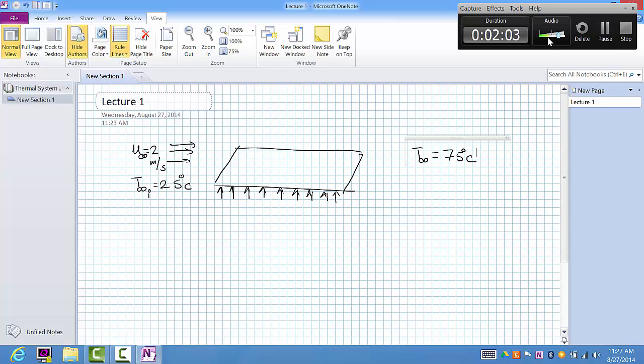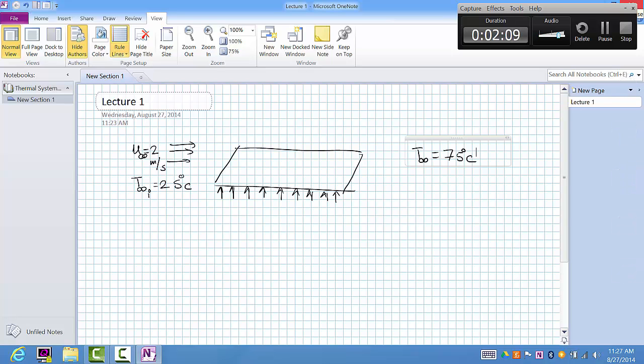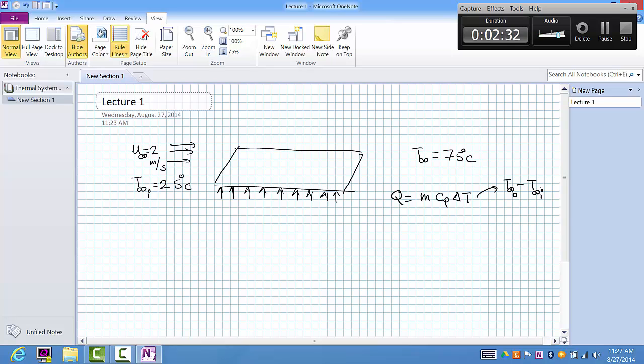You can draw on your thermodynamics knowledge and readily calculate the required heater capacity. The rate of heat required is Q-dot = m-dot · cp · ΔT, where ΔT is the outlet temperature minus the inlet temperature. You can calculate cp from thermodynamic property tables, evaluating it at the average temperature of the inlet and outlet.